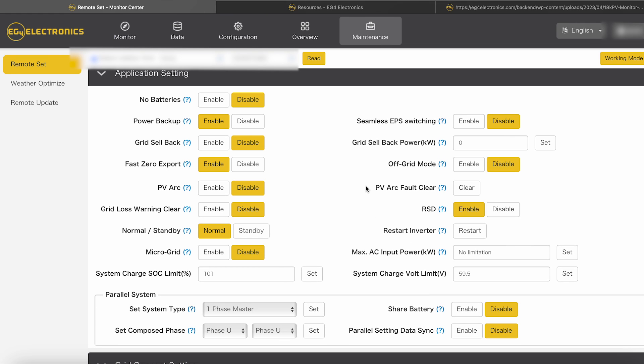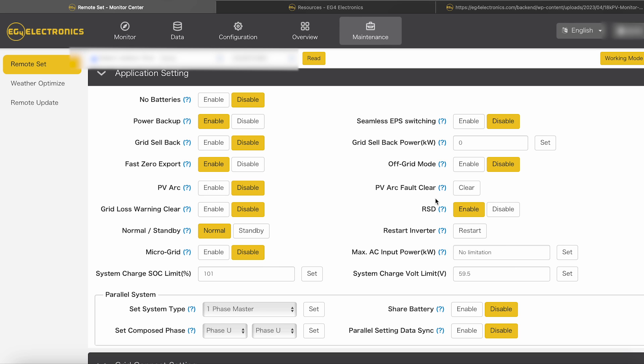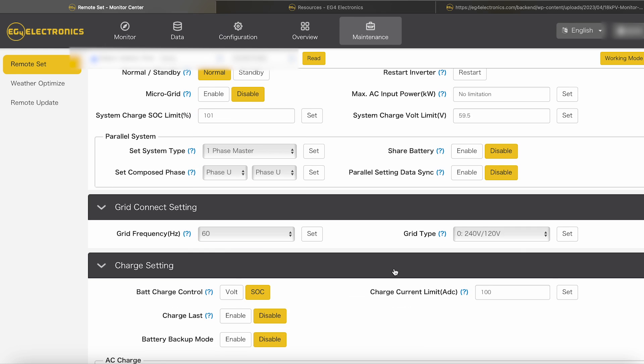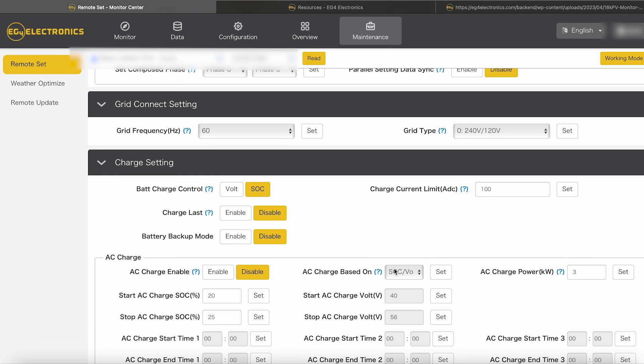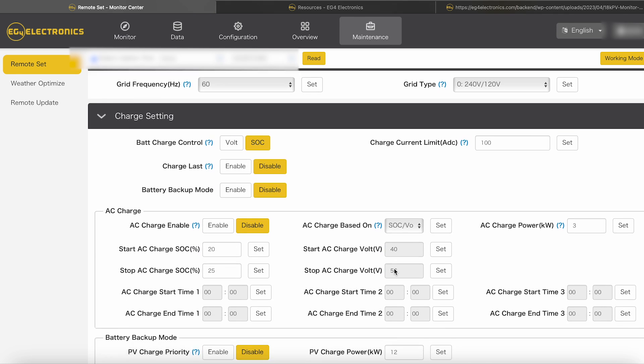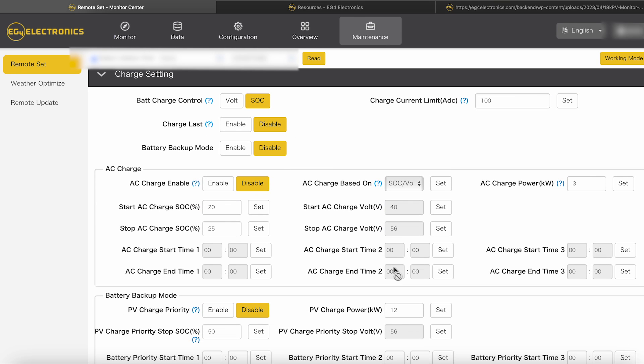Then we're going to go into your application settings. So no batteries. Of course, I got that disabled. Power backup on this is enabled. Grid sellback is disabled. The fast zero export, I got it enabled. PV Arc disabled. Grid loss warning disabled. The normal standby, I got it in normal. Micro grid disabled. Seamless EPS switching, I got it disabled. Off-grid mode disabled. RSD enabled. Then the shared batteries, I don't have any of that enabled. Grid connection, I didn't change anything with that. It's automated.